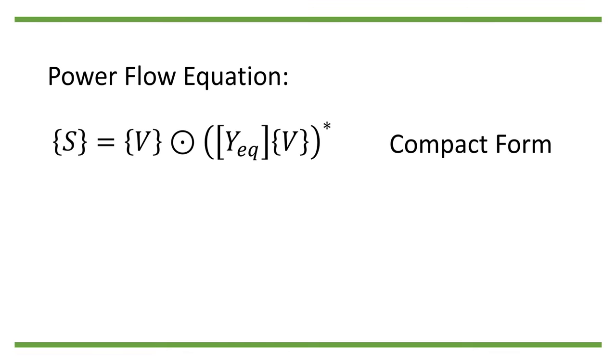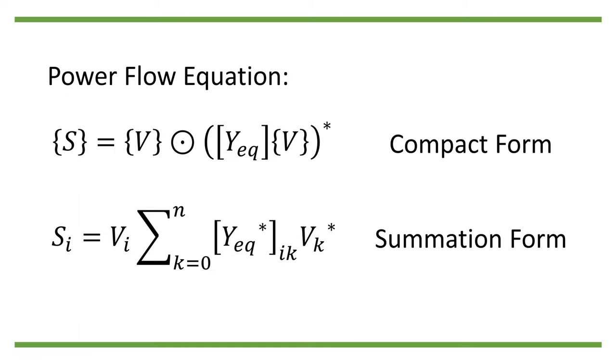We have seen the power flow equation in the compact form: S equals V entry-wise dot Y_eq V conjugate. To solve the power flow equation, it would be better to write the equation in the summation form. For every node i, S_i equals V_i times summation of k from 0 to n of Y_eq_ik conjugate times V_k conjugate.